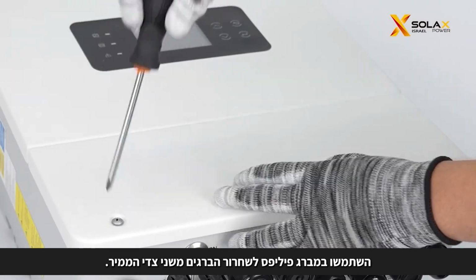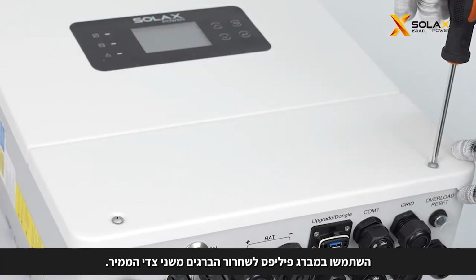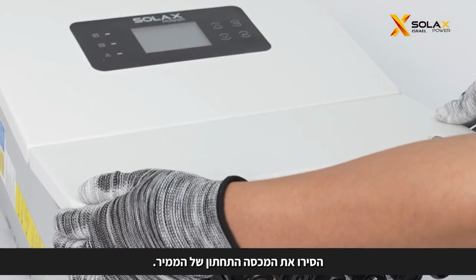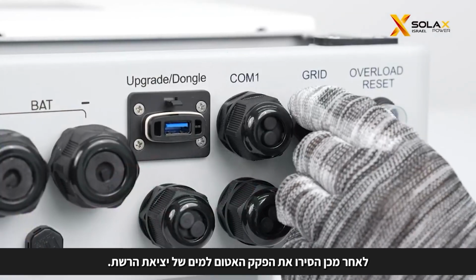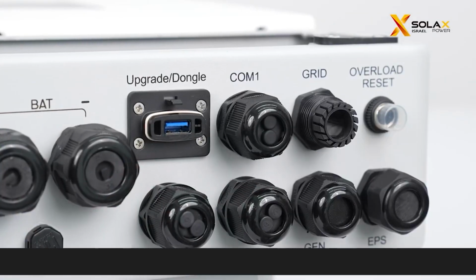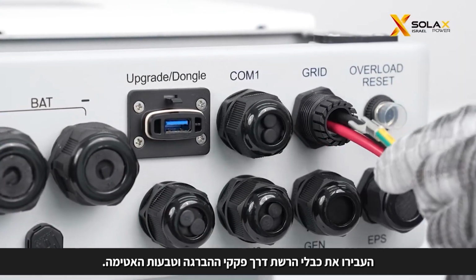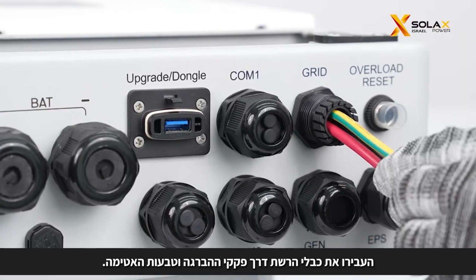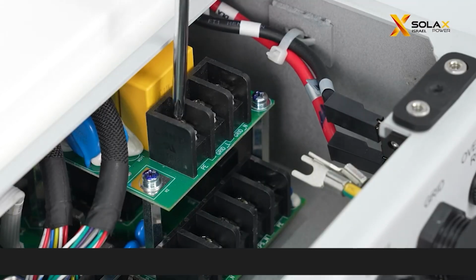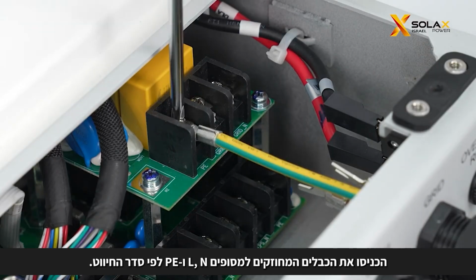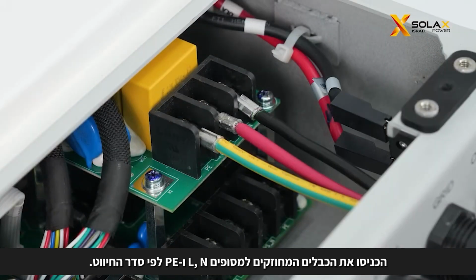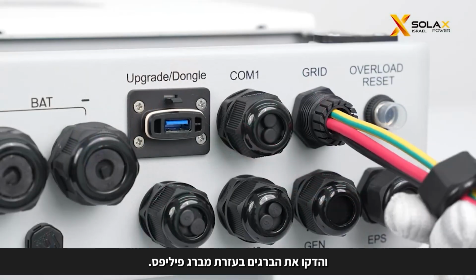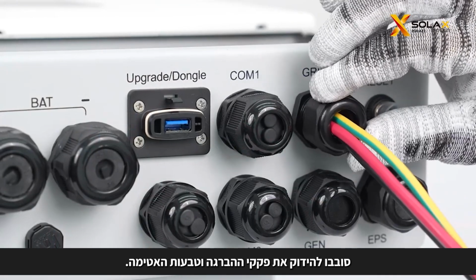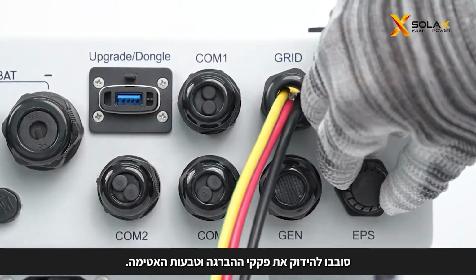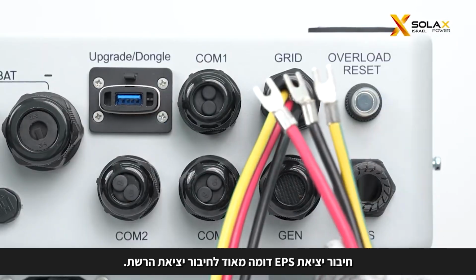Use a cross screwdriver to loosen the screws on both sides of the inverter. Remove the lower cover of the inverter. Then remove the waterproof plug of grid port. Pass the previously prepared grid cables through the corresponding screw caps and seal rings. Insert the crimped cables into the corresponding L, N, and PE terminals according to the wire sequence and tighten the screws with a cross screwdriver. Twist to tighten the screw caps and seal rings. The connection of EPS port is similar to the grid port.